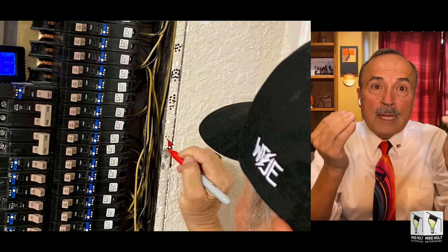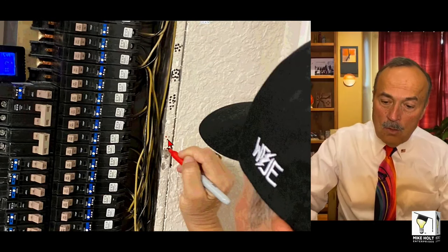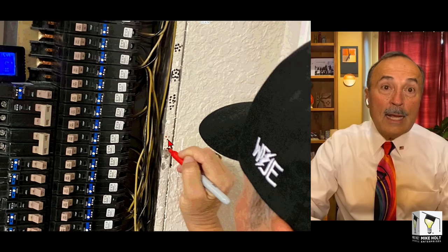If you have AFCIs tripping and you go in and do a service call, say, you're all good, and like, oh, fine. Then a week later, it trips again. Here's what I tell you to do. Tell them to get some way to mark on the cover. Of course, you're not going to take the cover off. Mark on the cover every single time they turn that back on, so you can get there and know which circuit tripped and how often. So hopefully that answered the question as to why I did that.